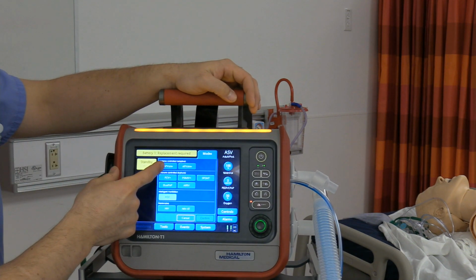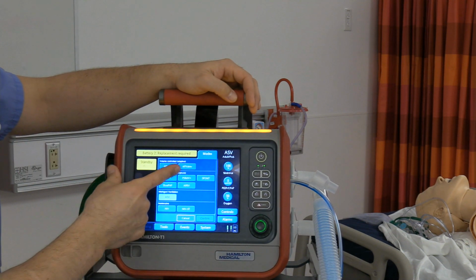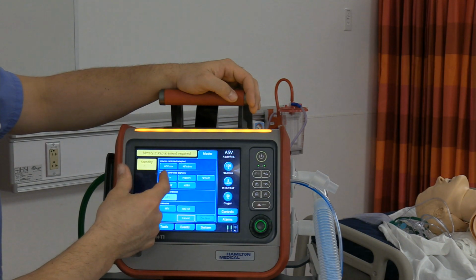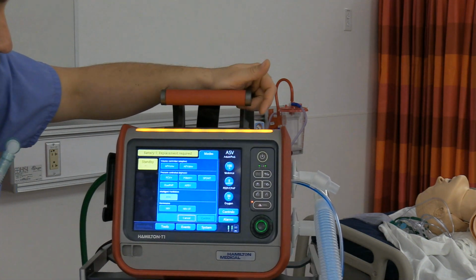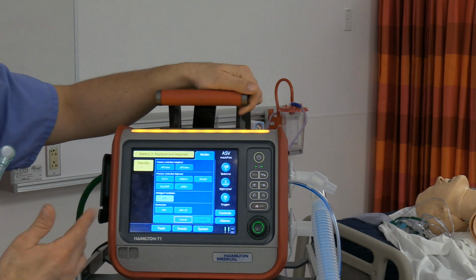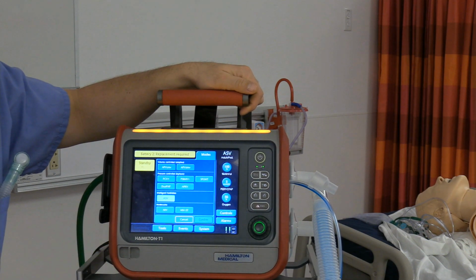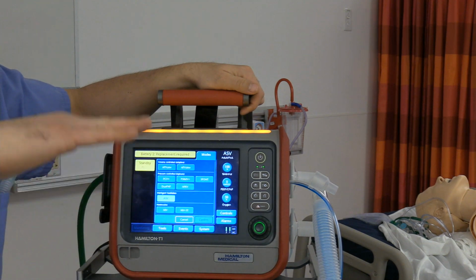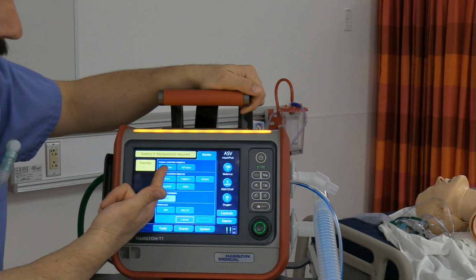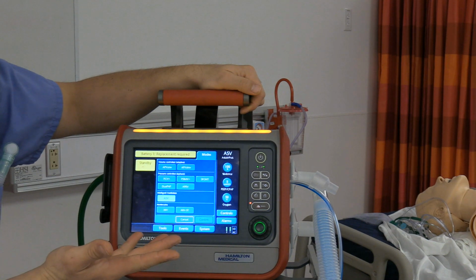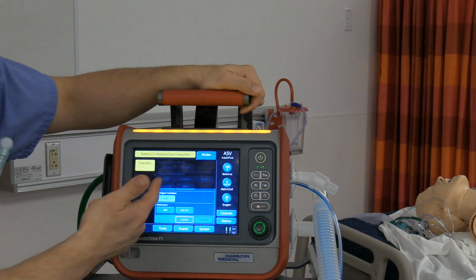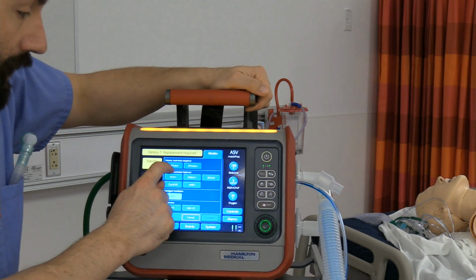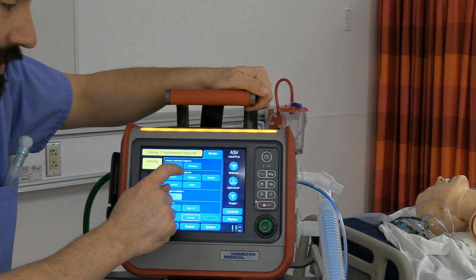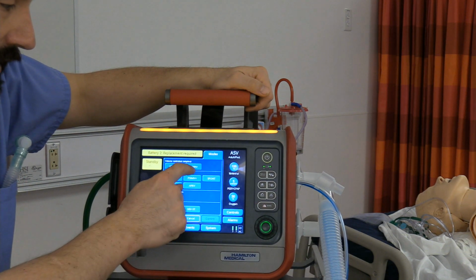The way that this vent's broken down, you have volume targeted ventilation. So I want to be very, very clear: this particular ventilator does not deliver true volume ventilation. You set a target tidal volume, but it does adjustable pressure ventilation. You'll see a couple of different terms. I have ours set to the standard Hamilton terms: APV, adaptive pressure ventilation, and then we have CMV as your mode selection, and SIMV.